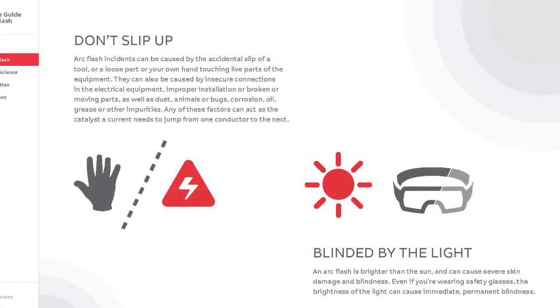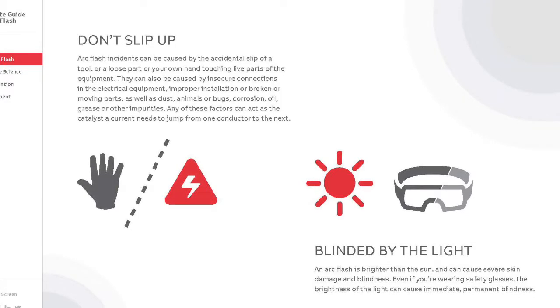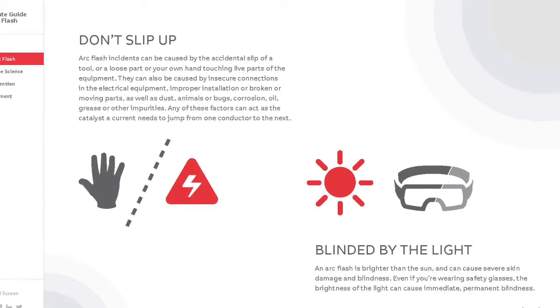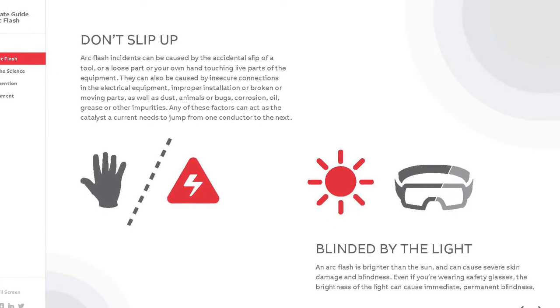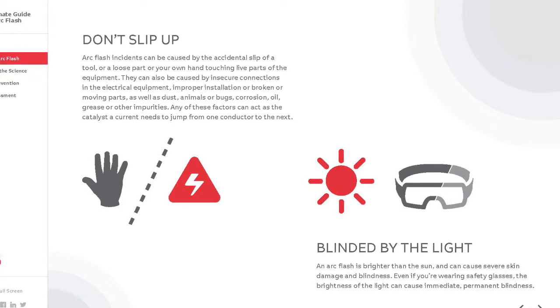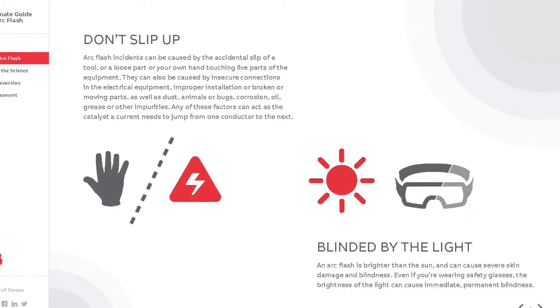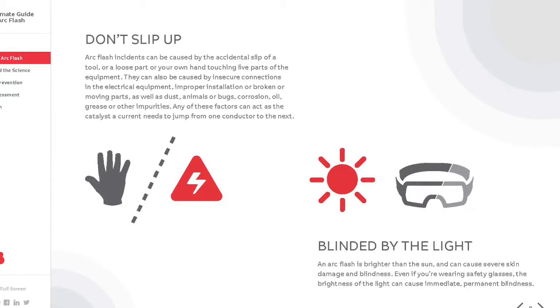Arc flash incidents can be caused by the accidental slip of a tool, insecure connections in the electrical equipment, improper installation, broken moving parts, dust, animals, bugs, corrosion, oil, grease, or other impurities. Any of these factors can act as the catalyst a current needs to jump from one conductor to the next.